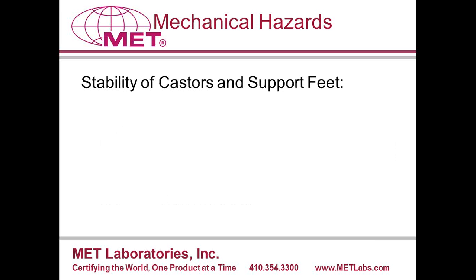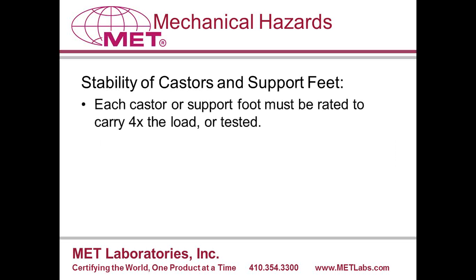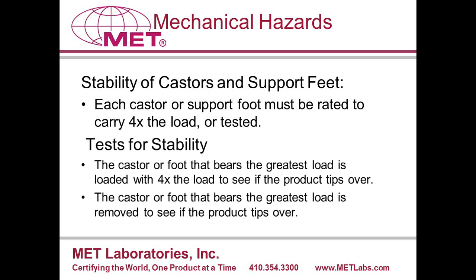There are new criteria for stability in the third edition standard related to support feet or casters. They need to be rated for 4 times the normal load or tested to be sure that the product won't overbalance if a foot or caster fails.